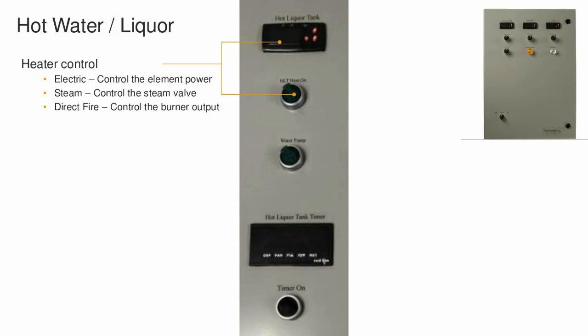In the case of electric, we'd be controlling the power going to the elements. In the case of steam, we'd be controlling the valve sending steam to your jacketed tank. And in the case of direct fire, we can control the burner output, with a constant feedback loop measuring the temperature in the tank and then turning on the electric, steam, or direct fire to get us back up.